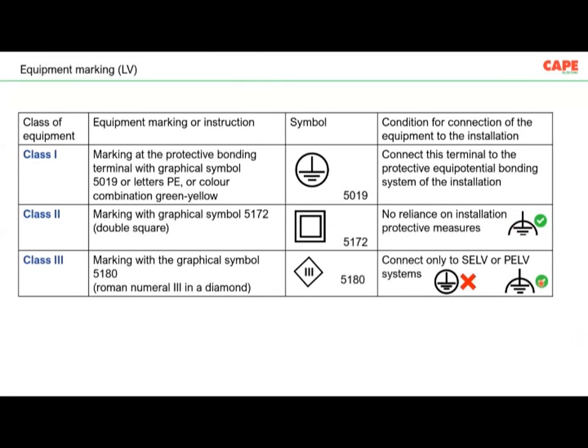Similarly, the third one, class 3 equipment. Class 3 equipment means it is an extra low voltage equipment operating with less than 50 volt AC or 120 volt DC. This equipment, of course, doesn't require protective earthing. The 5019 is not required, but the functional earthing is required. So basically, an equipment has its own requirement, like 5019, 5018, or 5020.